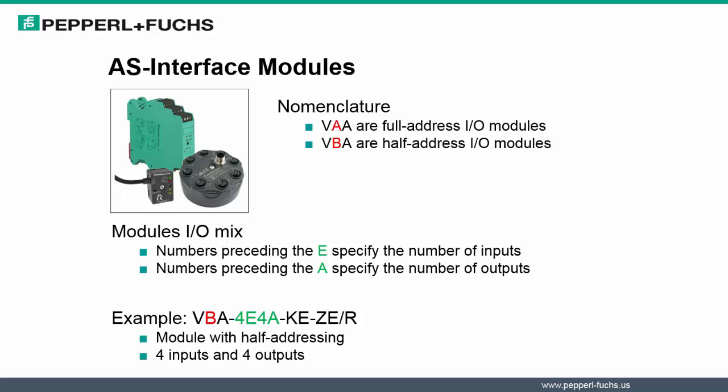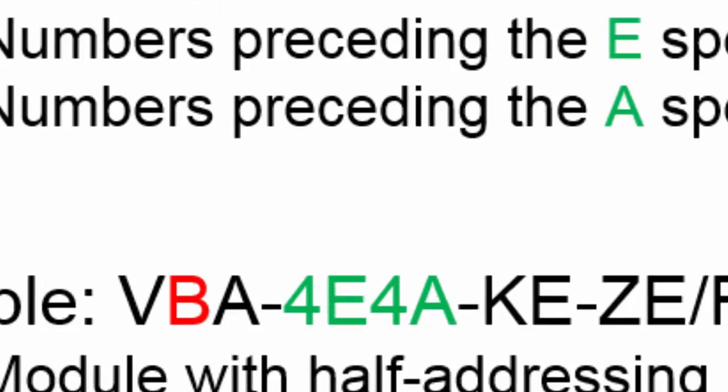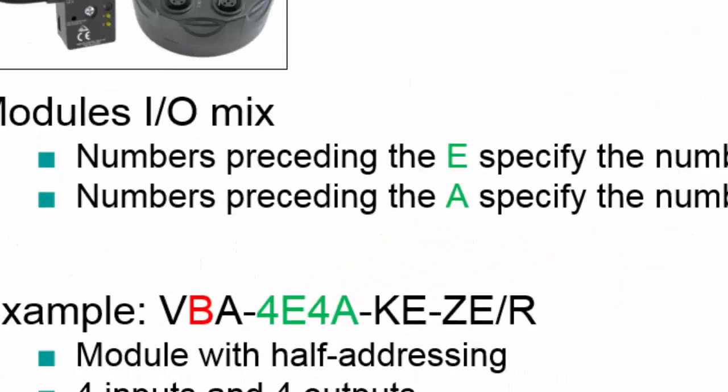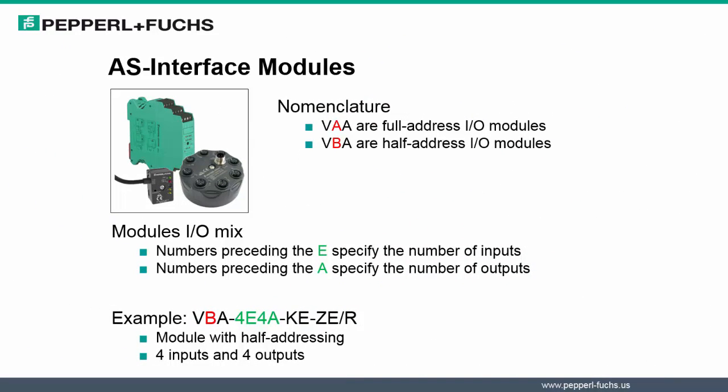Nomenclature can also help determine the I/O mix of a module. As we look at our slide, our example shows a module listed as a VBA-4E-4A module. In the first half of the nomenclature, the VBA indicates that the module is a half-addressable module. As we look further in the part number, the 4E-4A signifies the number of inputs and the number of outputs associated to the module.